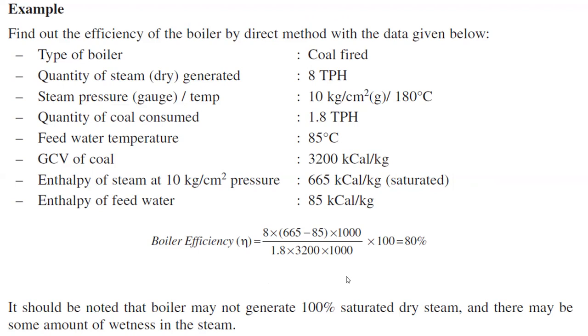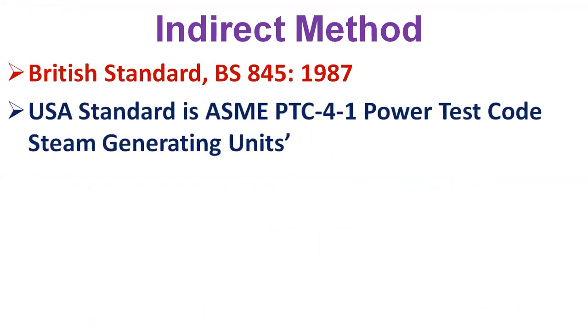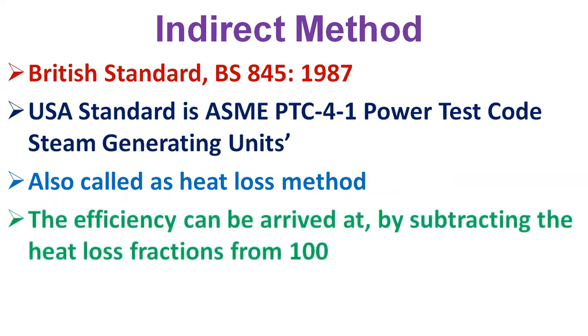It should be noted that a boiler may not generate 100% saturated dry steam and there may be some wetness in the steam — that is an important point for consideration. For the indirect method, reference standards for boiler testing at site include the British Standard BS 845 (1987) and the USA standard ASME PTC 4.1 — Power Test Code Steam Generating Units. The indirect method is also called the heat loss method, where efficiency is arrived at by subtracting the heat loss fractions from 100. The standards do not include blowdown loss in the efficiency determination process. Practicing energy managers in industry prefer simpler calculation procedures.